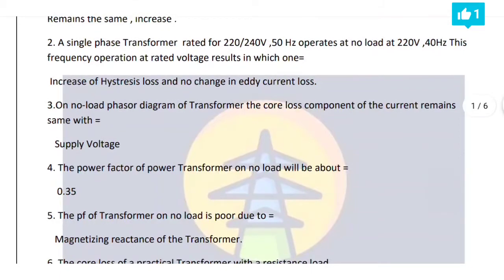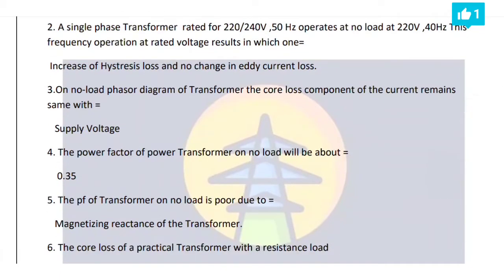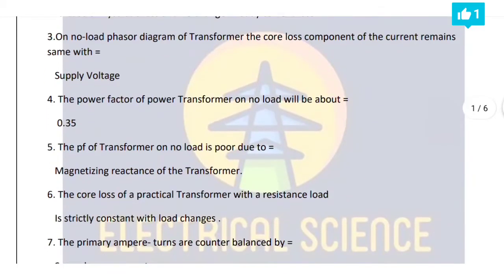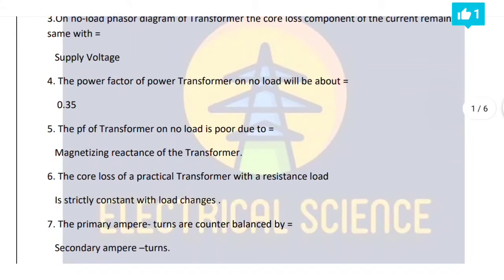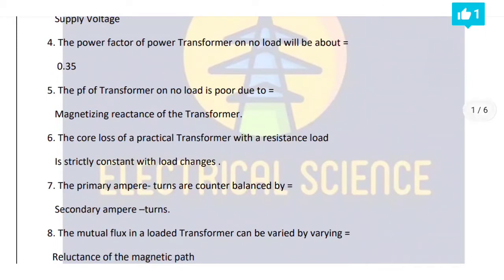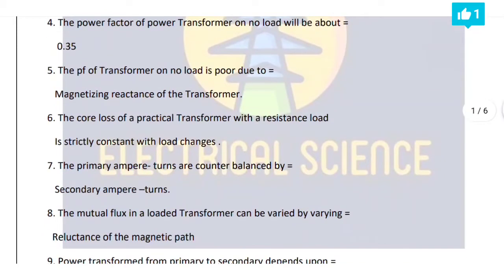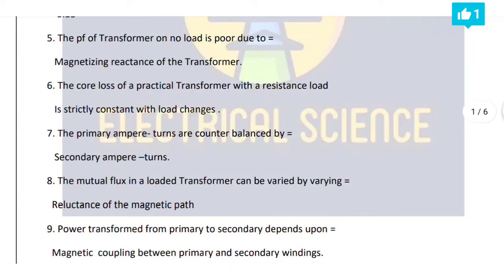Okay. Third point, on no load the phasor diagram of a transformer, the core loss component of the current remains same with supply voltage. Fourth point, the power factor of a power transformer on no load will be about 0.35. Okay. Fifth point, the PF of a transformer on no load is poor due to magnetizing reactance of the transformer. Okay. Sixth point, the core loss of a practical transformer with a resistance load is strictly constant with load changes. Okay. Seventh point, the primary ampere turns are counterbalanced by secondary ampere turns.